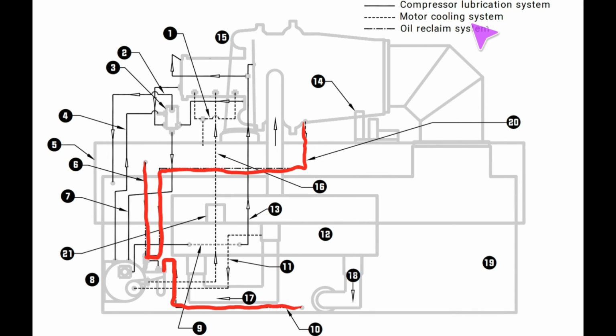They came in, got it installed, started it up, and all the oil disappeared. That was because the oil return side of the system wasn't functioning properly. He had a valve that wasn't working right, and it was causing the oil to not get returned back to the sump. It's very, very critical that you keep up with this side of the system.